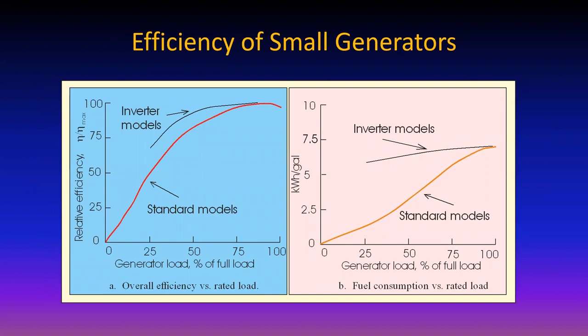Small generators, as mentioned earlier, are not very efficient at small fractional loads, and their maximum efficiency is around 90% load. That's because they have to maintain their 3600 or 1800 RPM rotational speed by burning gasoline or diesel.